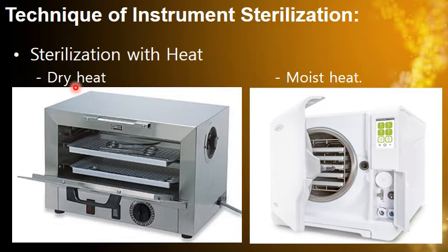As I said, there are some factors that should be followed with the dry heat. The first, the warm-up time for the oven, I should take into consideration, and the heat conductivity of the material. So I must not overcrowd the instruments, for all the instruments to be sterilized equally, and the airflow through the oven.